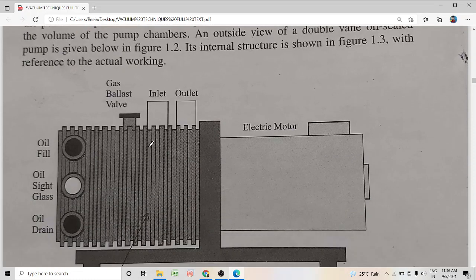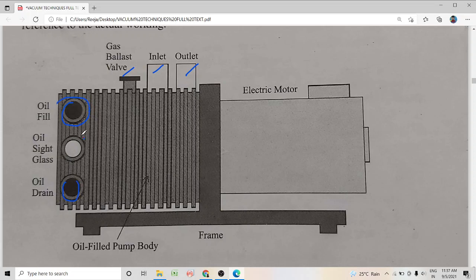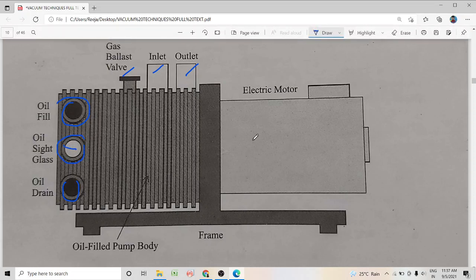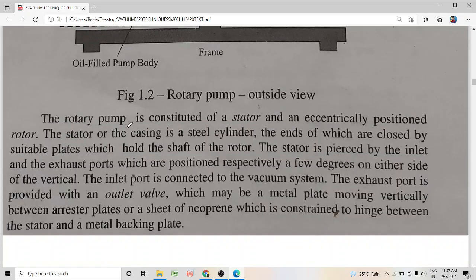This is our oil sealed rotary vane pump — this is how it looks from outside. There is an inlet, an outlet, a gas ballast valve, an oil fill valve, an opening to fill oil, an opening to drain oil, and an oil sight glass through which you can see the level of oil. There is an electric motor to rotate the shaft of the rotor. We will learn in detail the constituents of a rotary pump.